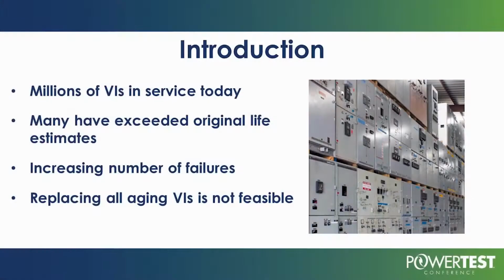This equipment went into service in the 70s and 80s, and we're now 50 years in, and we have to find a way to keep them in service 50 more years. That's 100 years. We have to find a way to keep vacuum circuit breakers in service for 100 years, and the vacuum interrupter is one of the key components of the vacuum circuit breaker. Many of these interrupters have already exceeded their life. There again, speculation, what is their life?